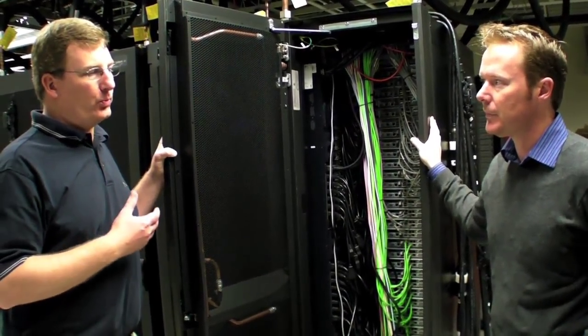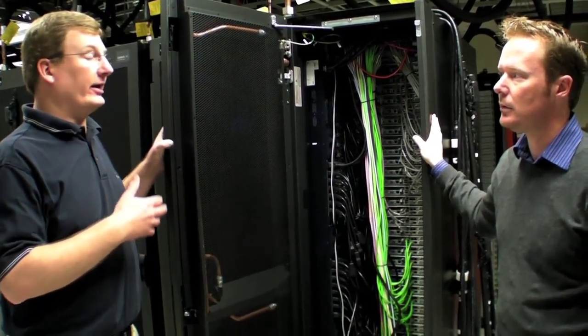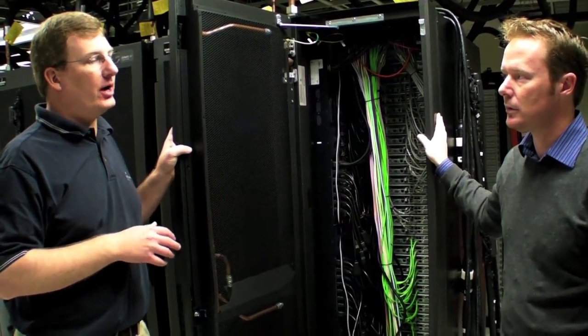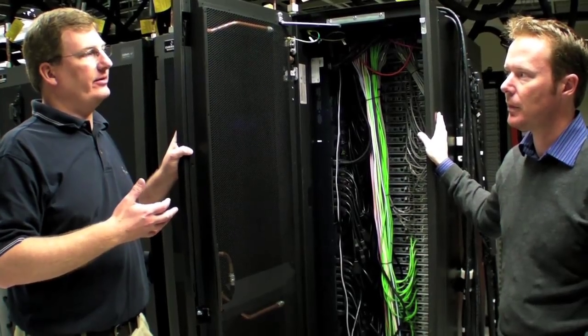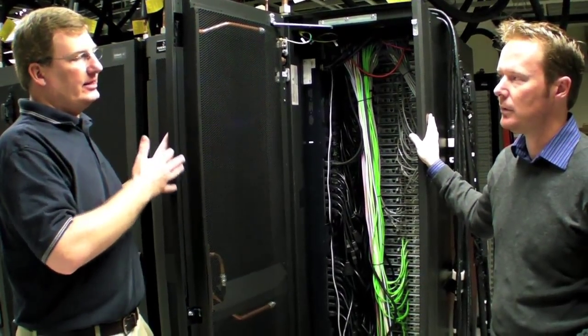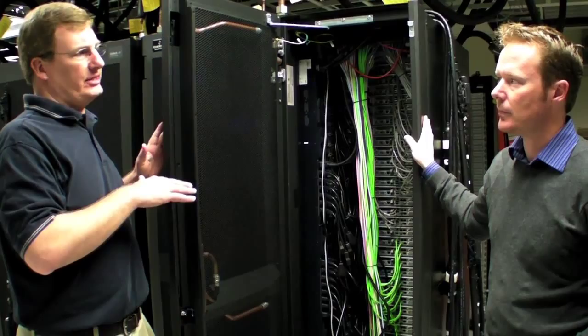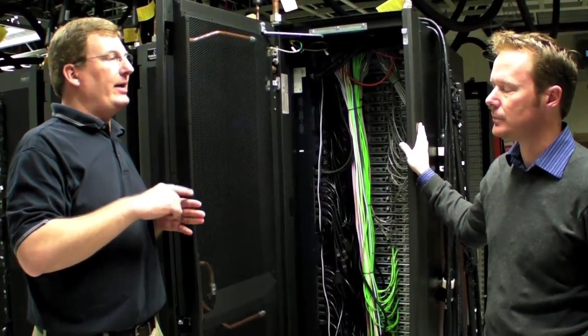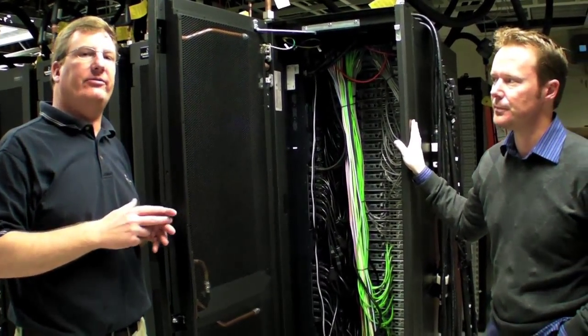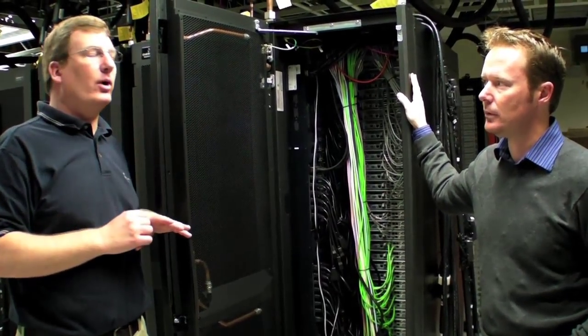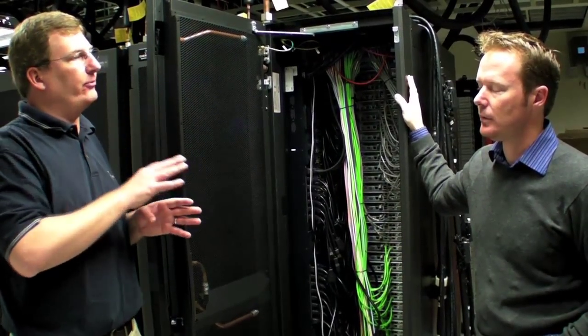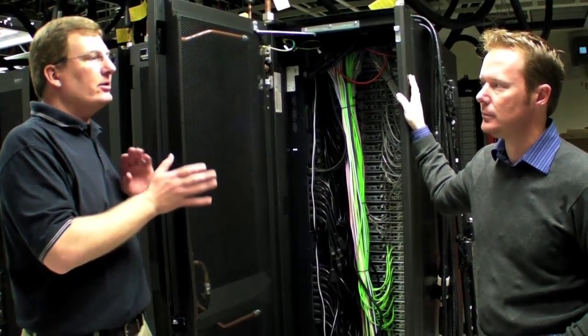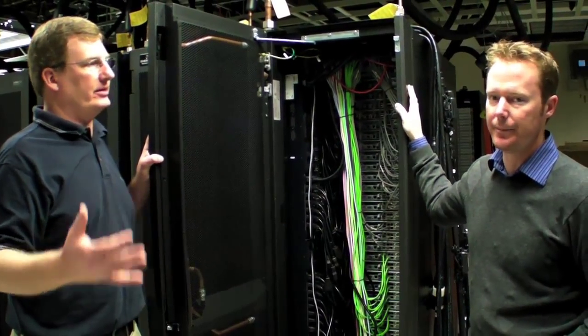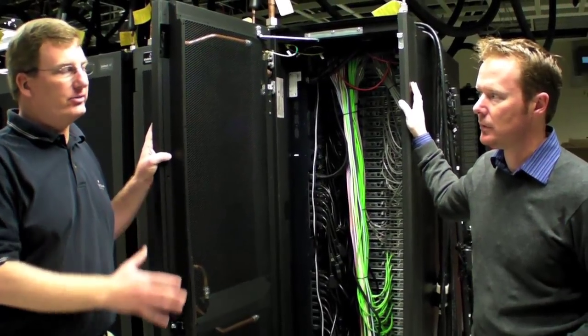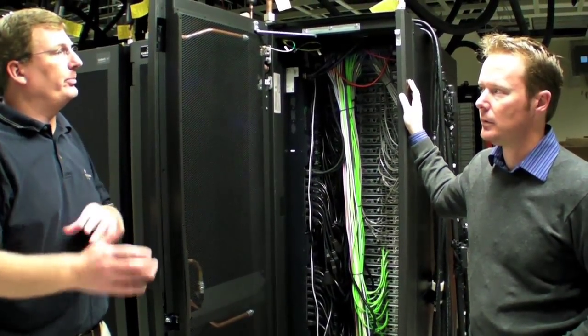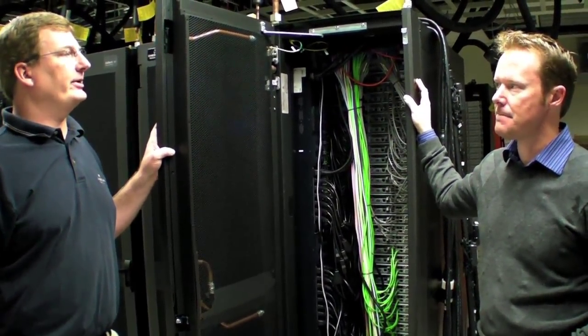Right, yeah. That will work if you have a hot aisle, cold aisle configuration as well. But typically the way we'd deploy these in the field is connecting these doors to alternating pump stations, so it might be an AB or ABC configuration. By doing that, if you bring one system down, the air will still mix before going into the next one, so you're not jetting really hot air into the next system. It kind of gives you built-in redundancy while you take something down for maintenance.